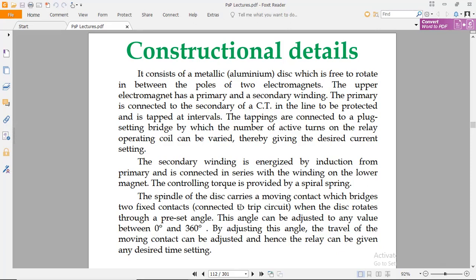The spindle of the disc carries a moving contact which bridges two fixed contacts of the trip circuit. When the disc rotates through a preset angle provided by the user, this angle can be adjusted to any value between 0 and 360 degrees, because the disc rotates through an angle from 0 towards 360 degrees. By adjusting this angle, the travel of the moving contact can be adjusted, and hence the relay can be given any desired time setting.